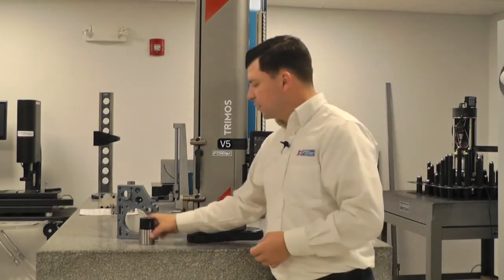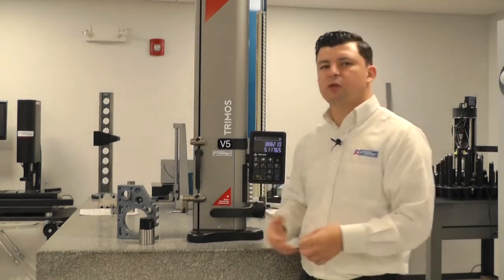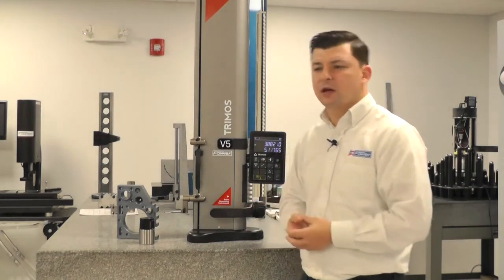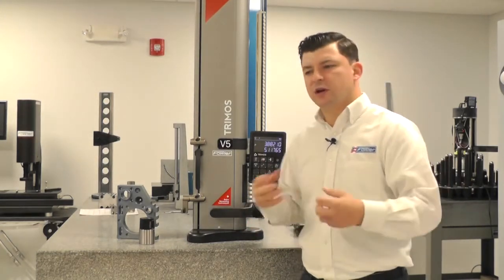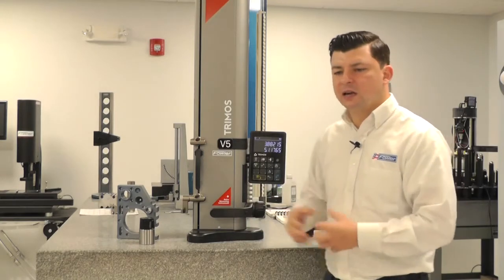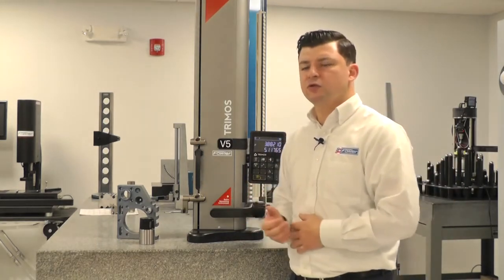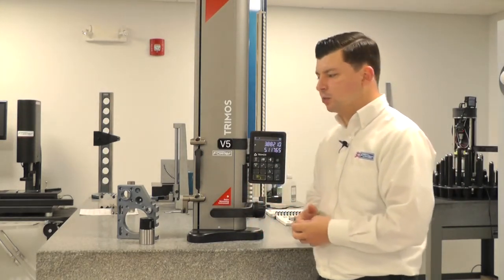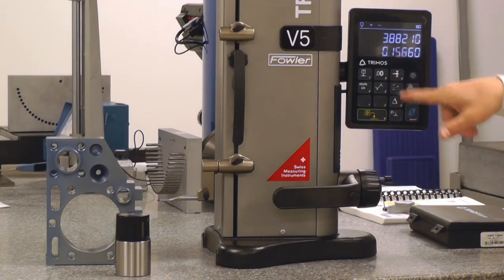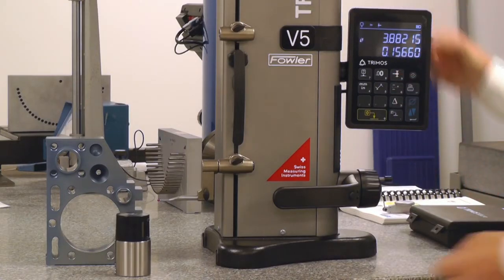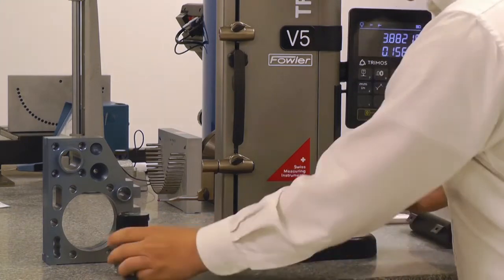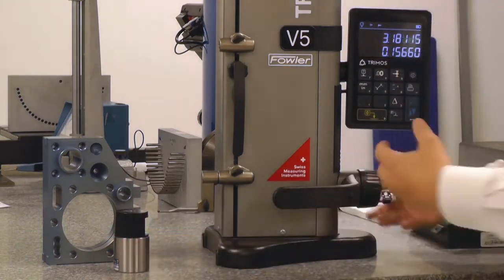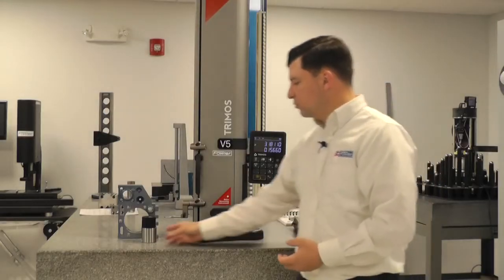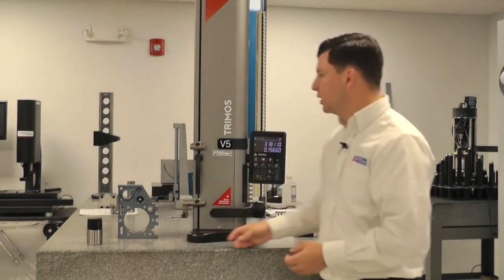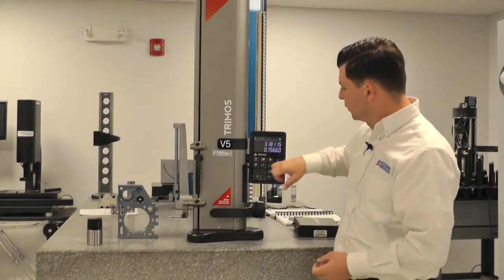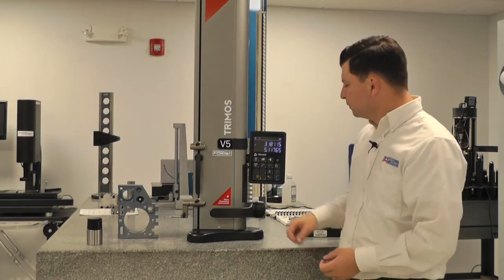We did our initial calibration in the beginning. If you need to change your probe in the middle of the process of measuring, to measure some small features, to measure some grooves, any of your different probe setups that you need to use once you've initially calibrated your initial probe, you simply hit the number 9 key, which prompts you to calibrate your probe. Again, we would go up and down to calibrate our probe. So this is how you're going to recalibrate a new probe in the new process with your probe button here, number 9.